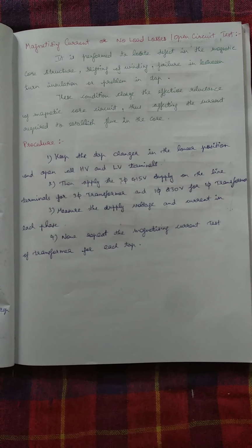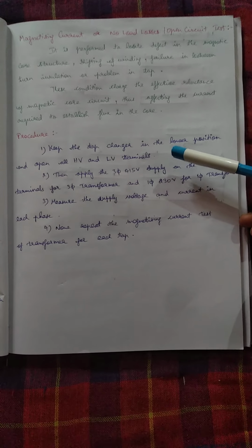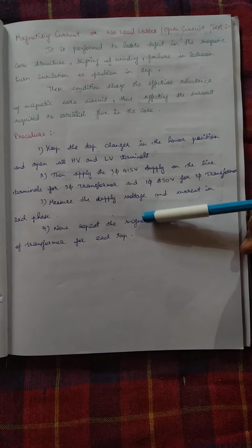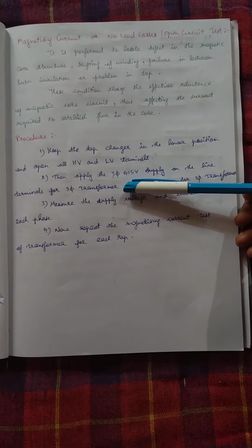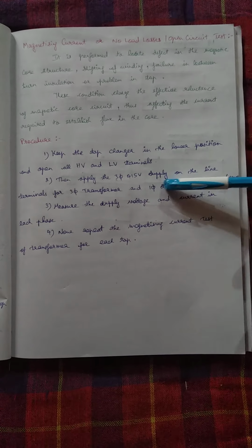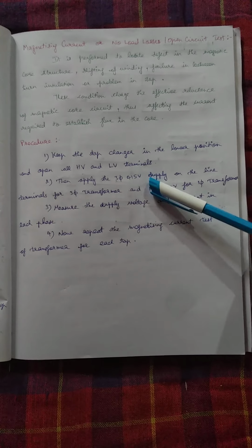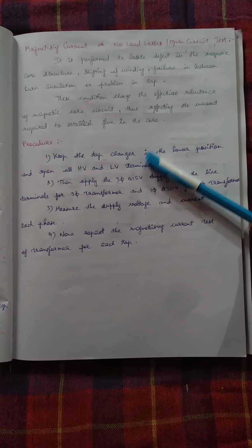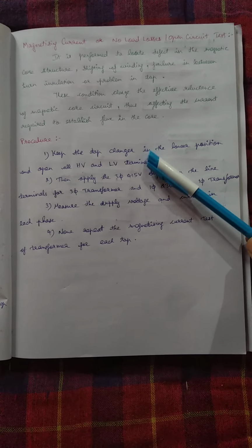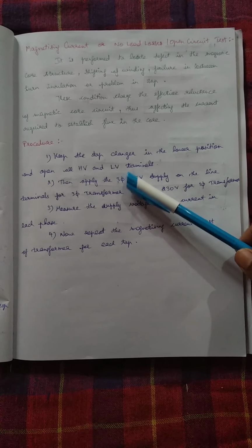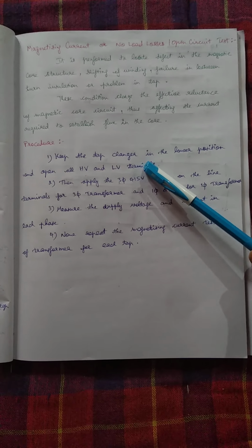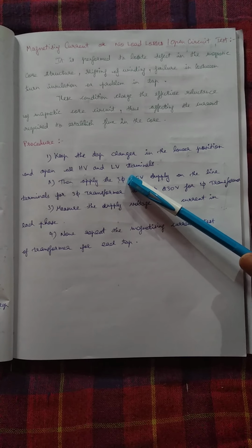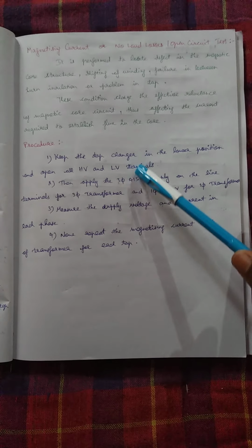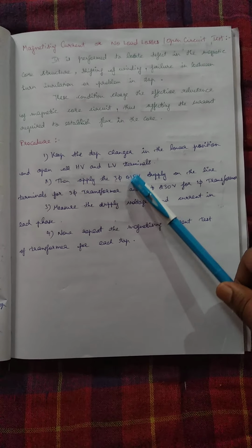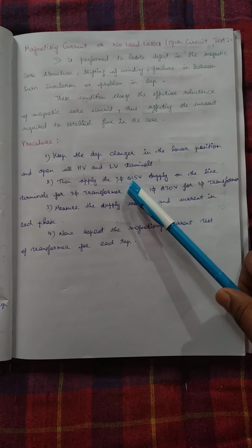Next, the procedure to be carried out during the test. First of all, we need to ensure that the primary and secondary are free from other sources, which means there should be no connection between the primary and the secondary, whether through jumpers or even the bushings. Then keep the tap changer in the lower position and open all the HV and LV terminals, which means the HV and LV terminals should have no source connected.